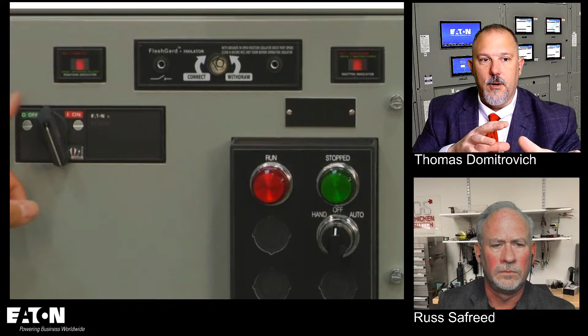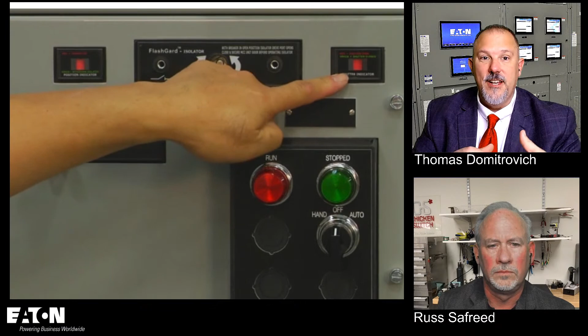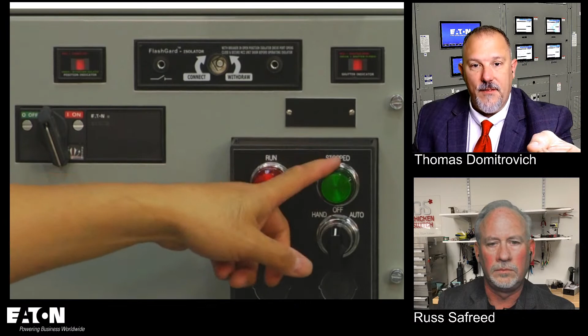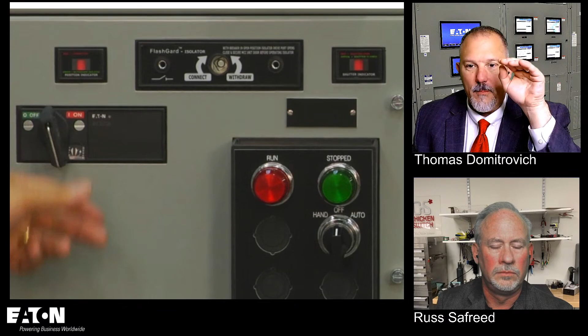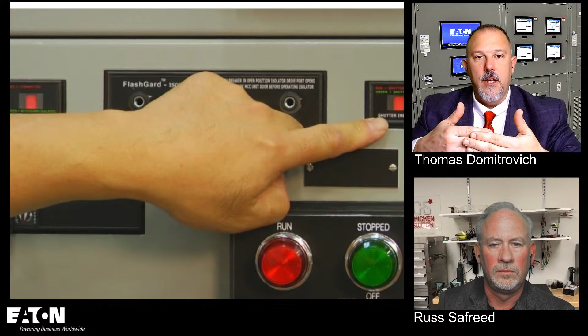And then what we do is take the front. You have your port, and you have to make sure it's in the off position, because you'll see in this short video where if he turns that switch to the on position, watch the little door in the middle. You can't plug anything in there to rack it off if it's on, so you have to have it in an off position. Then there are indicators on either side that tell you the level of engagement on the bus.